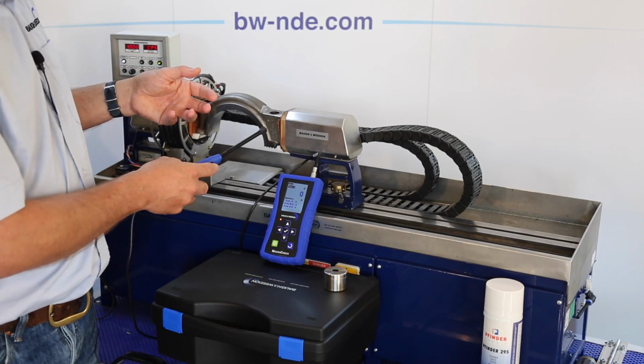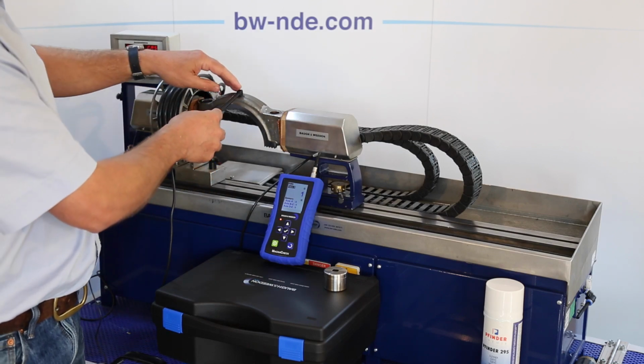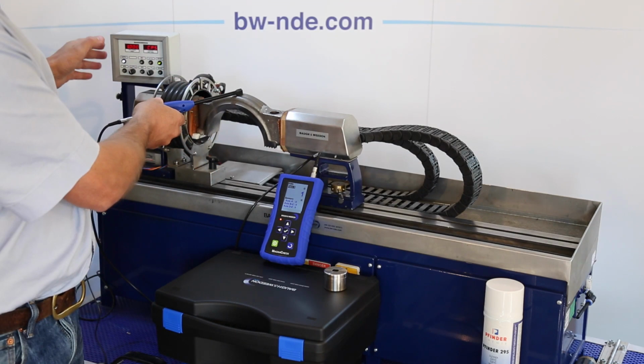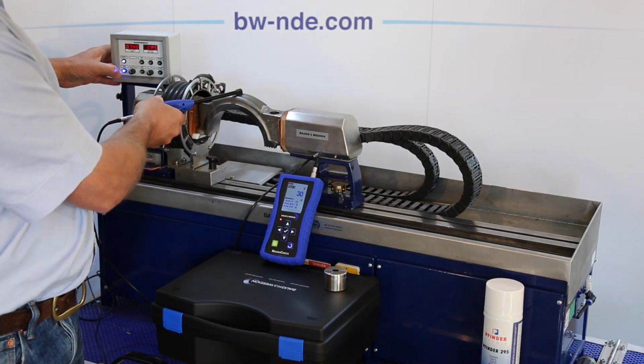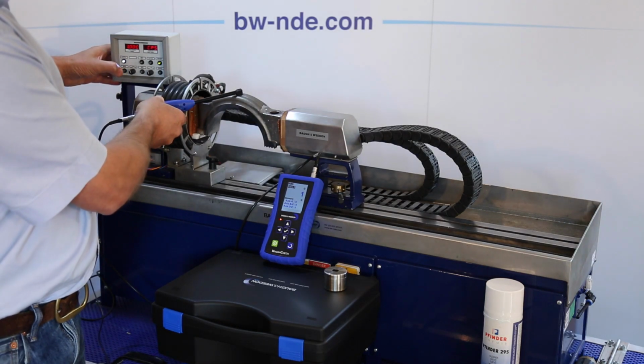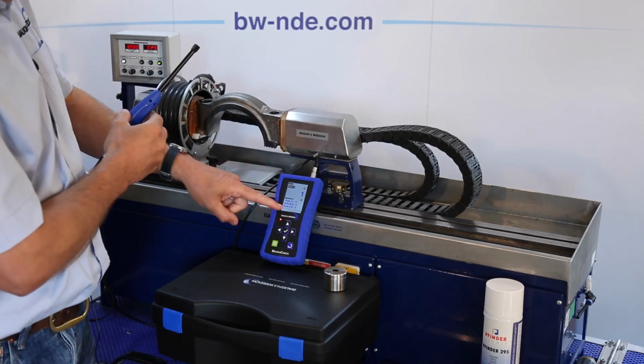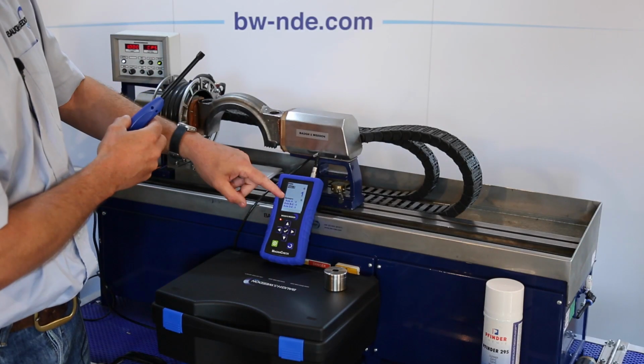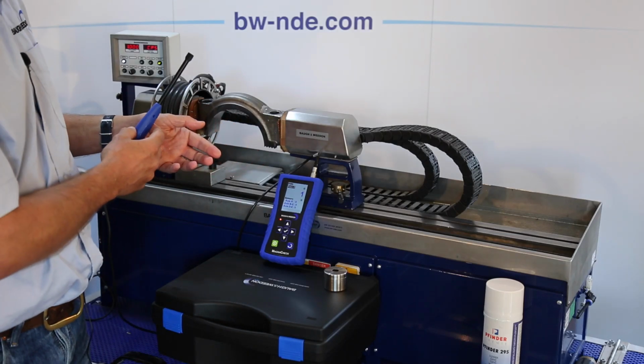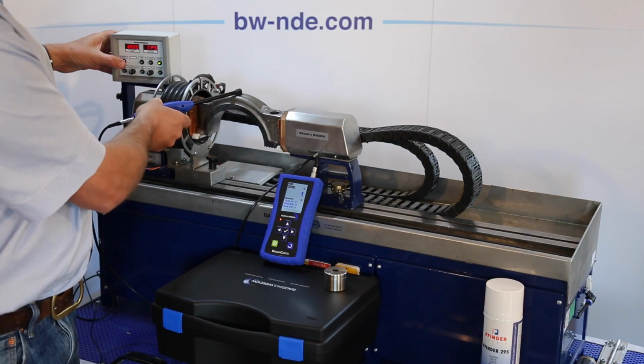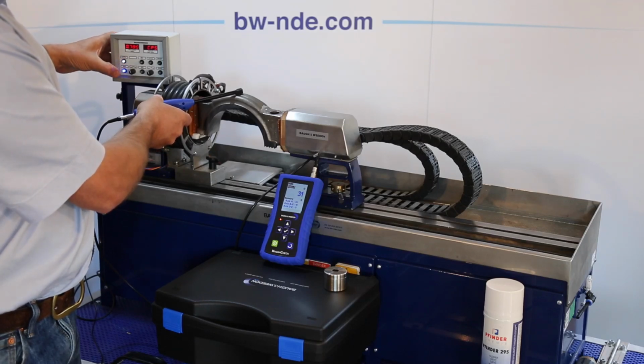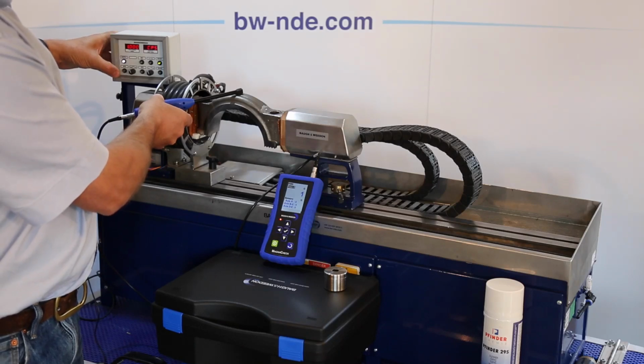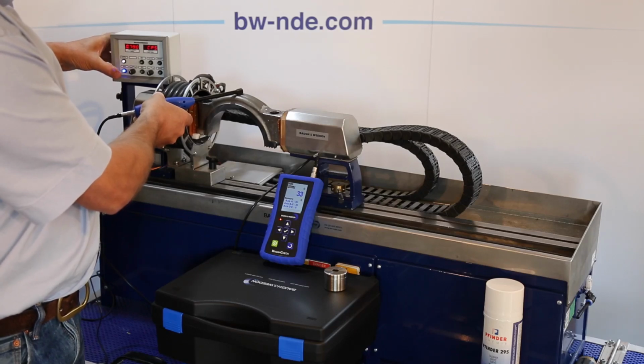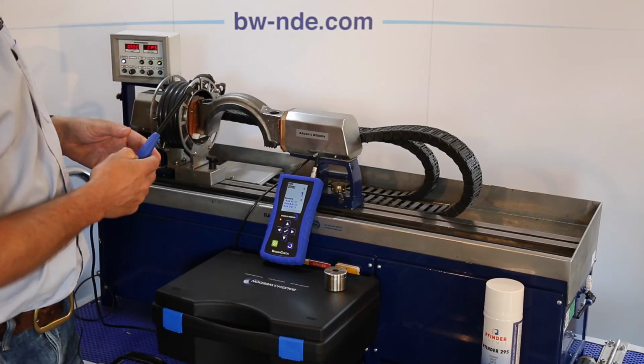The advantage of this machine in this mode is that if your probe is off at a strange angle, for instance 45 degrees, and you hit the button, you get the same amalgamated reading. In the small window at the bottom, the smaller figures, you can see the field strengths through each of your individual faces. So if I do that shot again with the probe at 45 degrees, it's showing me that I have roughly equal fields going through axis A and axis D to E, and my combined reading is as I'd expect it to be, about 33 Gauss, which is ideal for the test.